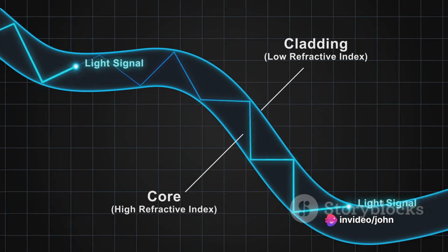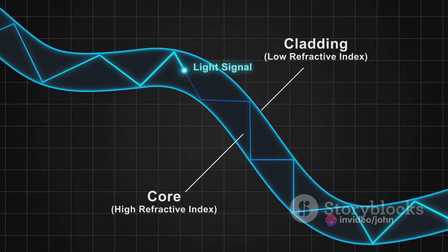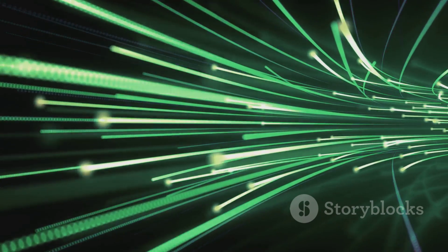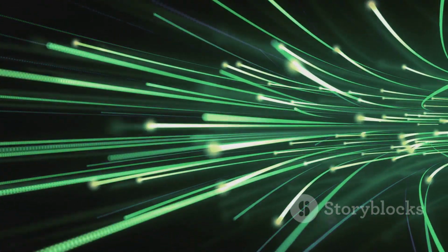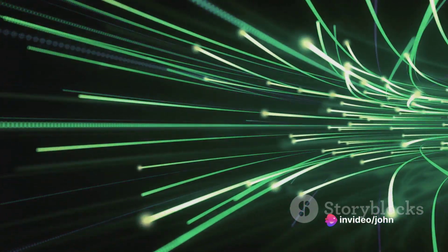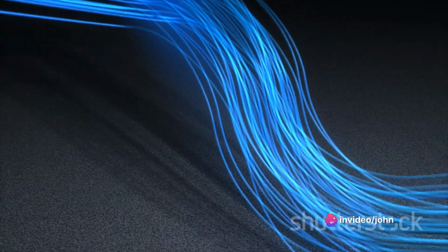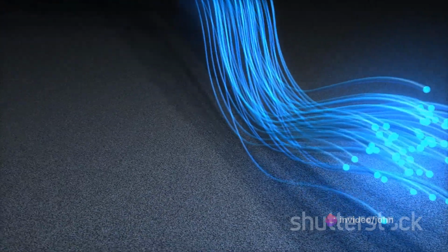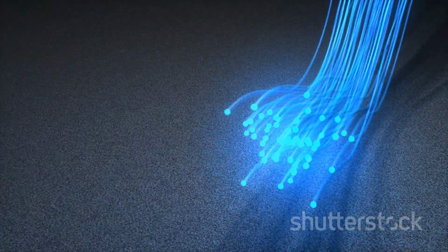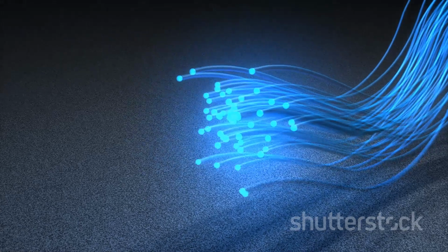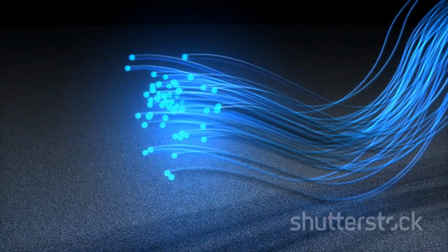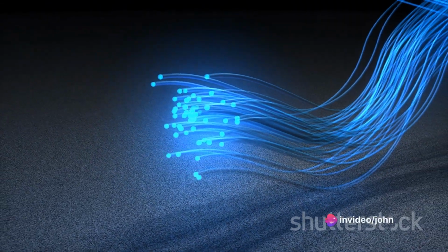The OTDR will send a pulse of light down the cable and measure the time it takes for the light to be reflected back. This time is then converted into distance, giving you the location of any flaws or breaks in the cable. After the test, you'll get a trace, which is a graphical representation of the test results. This trace shows the entire length of the cable with any flaws or breaks clearly marked. By analyzing this trace, you can determine the exact location and nature of any issues with your fiber optic cable.